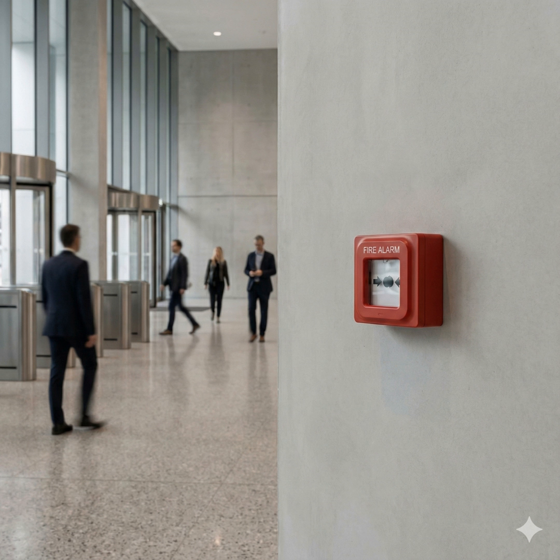This integration is so vital. It has to be seamless. This integration enables those crucial life safety smoke control sequences we mentioned. For example, detection in a machine room has to trigger an immediate HVAC shutdown in that area. Detection in an elevator shaft must activate elevator recall. And this all relies on sophisticated data exchange.